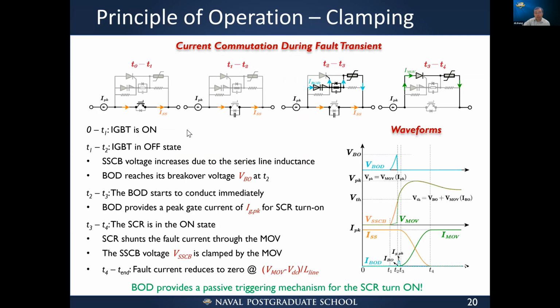So now the details of how the circuit works. First, the IGBT turns on and carries the current, and then we detect the fault. We turn off the IGBTs. When we turn off the IGBTs, the voltage across the two IGBTs will start to rise. We may add some snubbers there to make it softer and smoother. But this voltage will be shared by the thyristors and also the MOV. When the voltage shared by the breakover diode is high enough, the breakover diode will turn on. And then all the voltage at this point will be applied to the MOV. So the MOV's leakage current will increase to a few amps, if designed right. And this few amps of current can be high enough to trigger the thyristor, and then the thyristor will be turned on. Once the thyristor is turned on, the current will flow through the thyristors and through the MOVs. Of course, the MOV will start clamping the voltage.